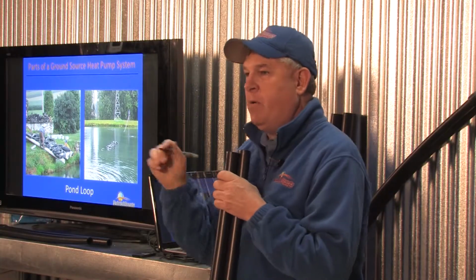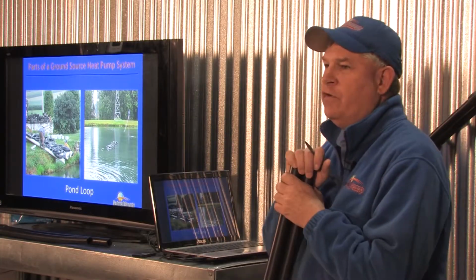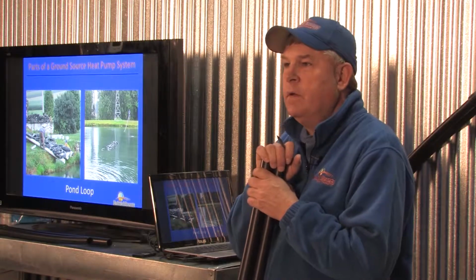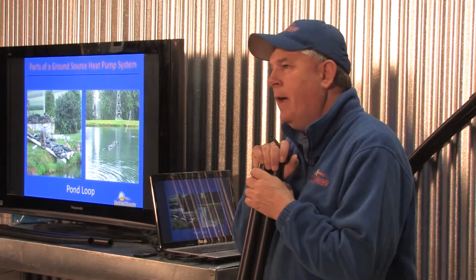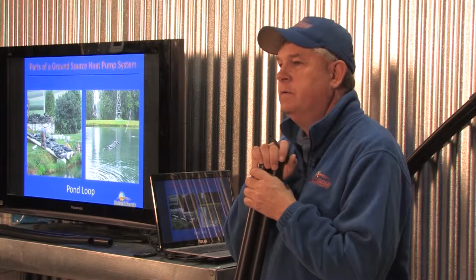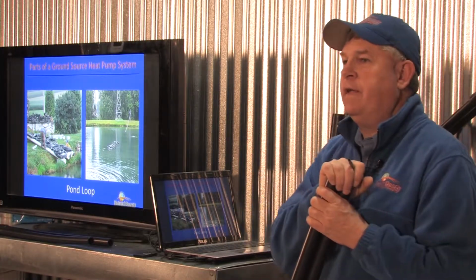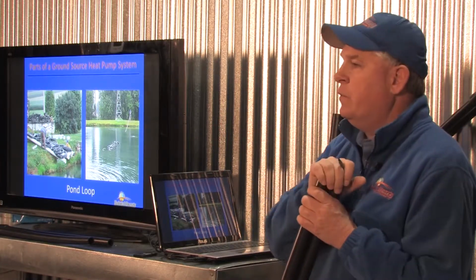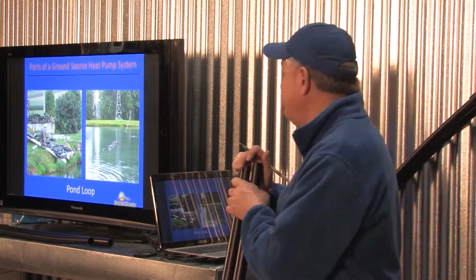Performance-wise, they'll all be the same. Question usually comes up, which one's better? Well, there's not better. Different doesn't always have to be better or worse. It's just different. They're all different, but they all should have the same operating results at the end. If there's a better, it's probably a pond loop, because I can get the same results with a lower installed cost. But that pond needs to be a minimum of 3/4 of an acre and at least 6 or 8 feet deep. That particular one was exactly an acre, 12 feet deep.